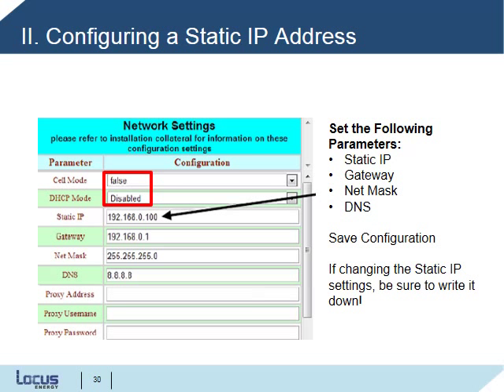Now, if you're setting up an Ethernet connection on a local area network that requires a static IP address, you can change these settings by logging in. In the Network Settings panel on the right-hand side of the configuration page, we'll be setting a number of parameters. The cell mode should be switched to false, and DHCP mode to disabled. You'll set the static IP address, gateway, netmask, and DNS. Hit the Save Configuration button, but before doing so, be sure to note the static IP address that you entered, as you won't be able to obtain this information after making these changes. After saving configuration, the LGate will be enabled to communicate using the programmed static IP address.